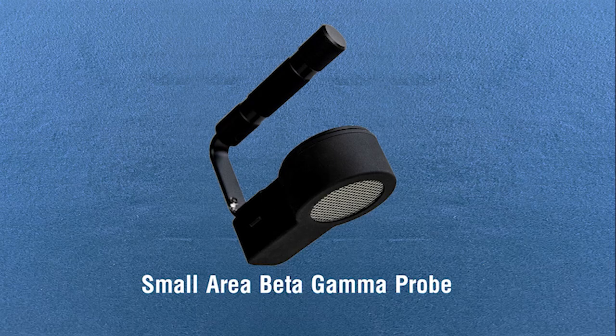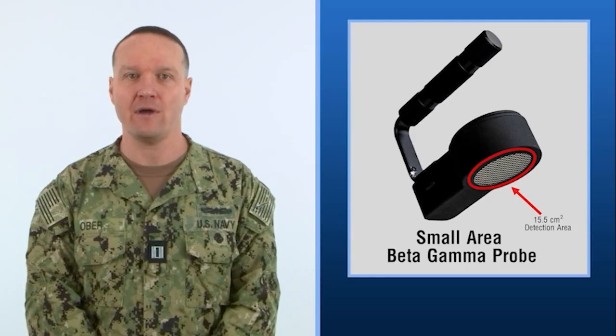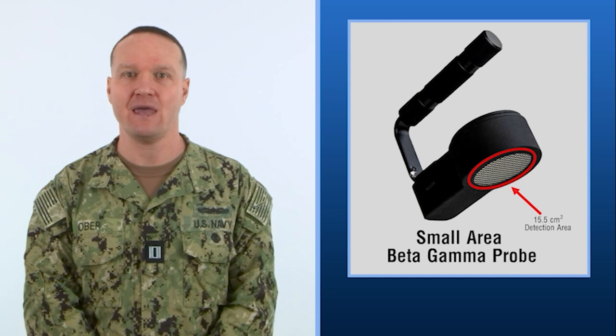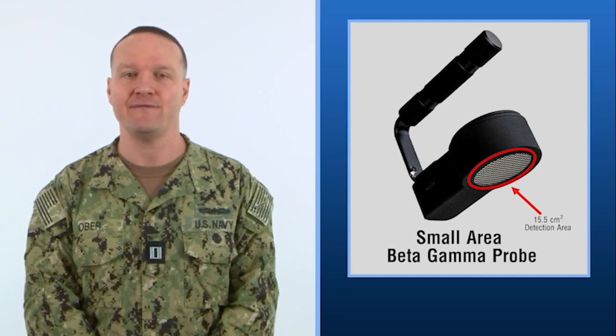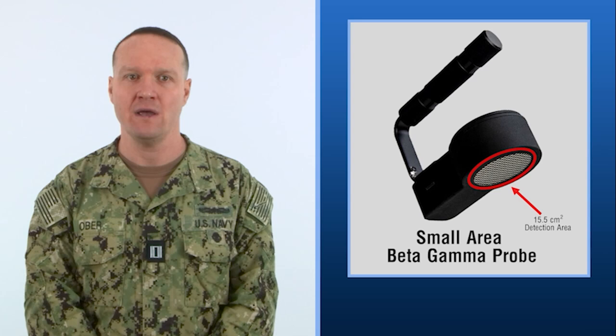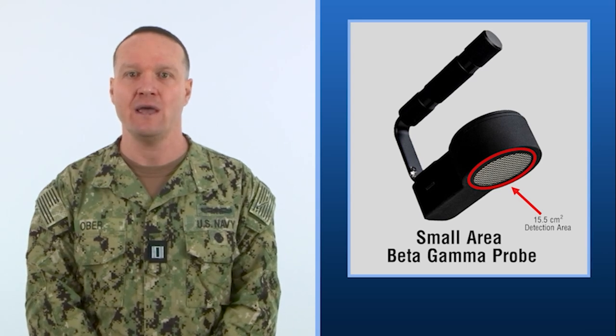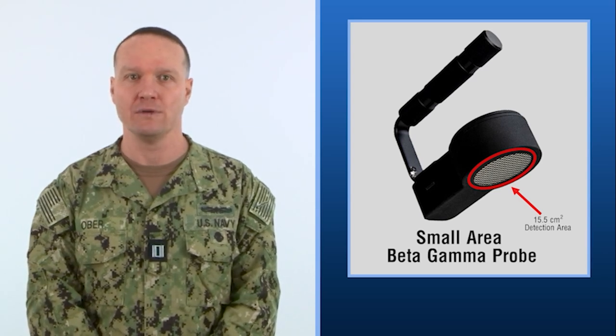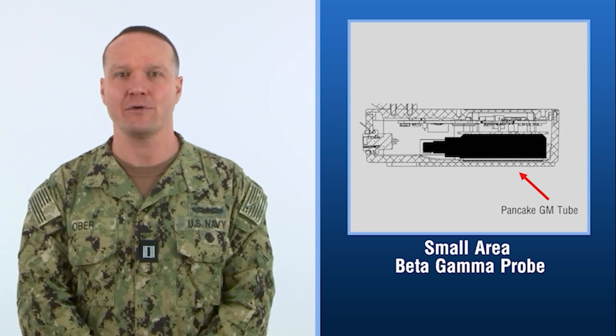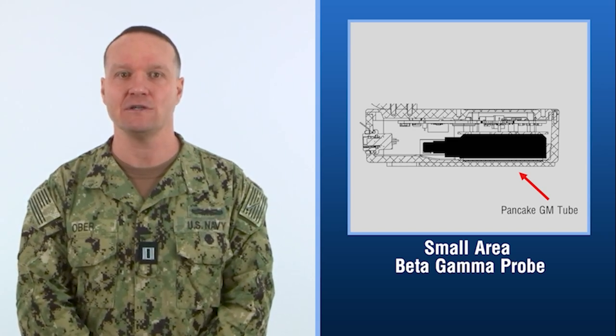Small area beta gamma probe. The small area beta gamma probe has a pancake configuration to provide a 15.5 centimeters squared sensitive detection area in a small and lightweight probe. The small area beta gamma probe detects beta and gamma radiation using a pancake GM tube. The probe is designed to be handheld and is suitable for operations looking for beta and gamma contamination. It can be used to search personnel or objects.